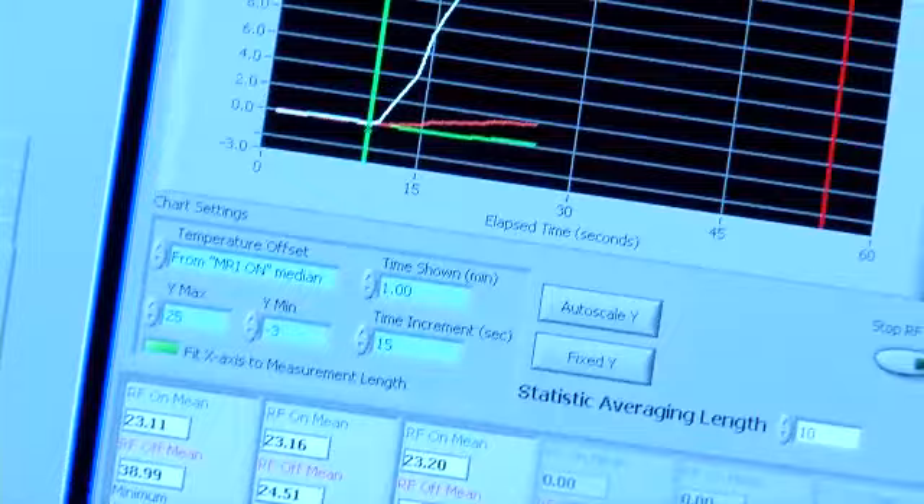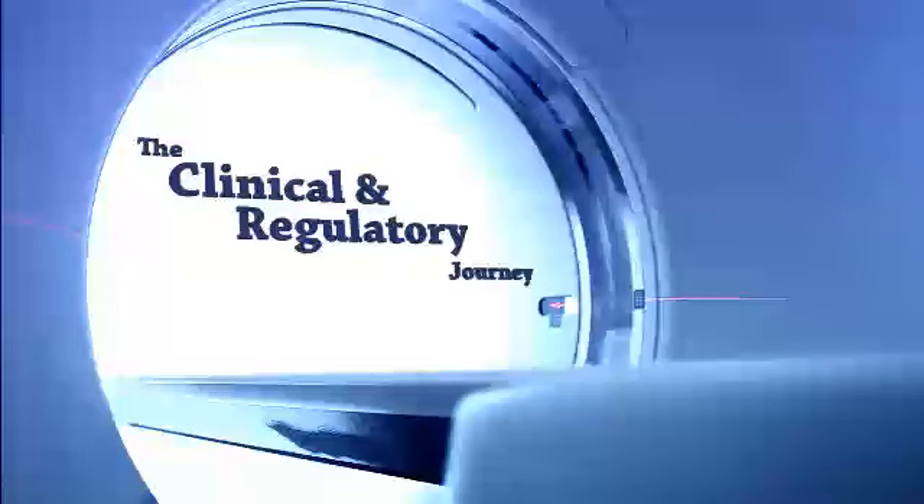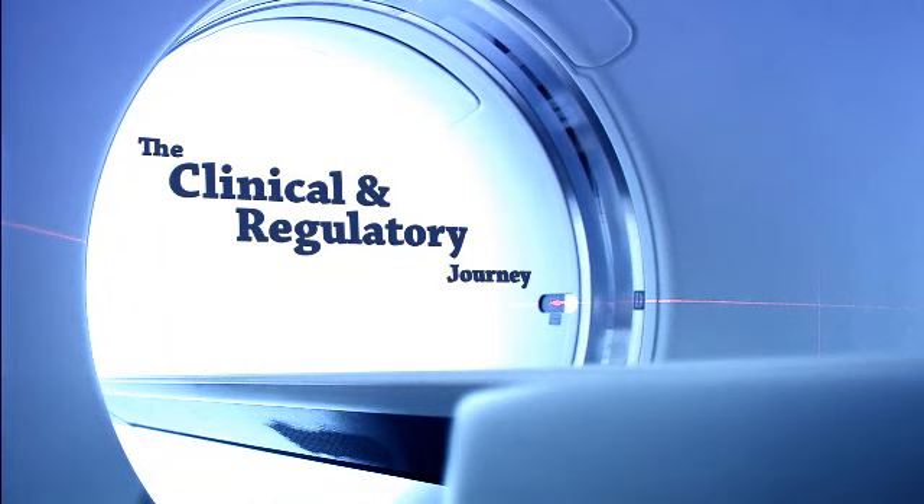We conducted over 1,500 measurements and compared each measurement to the simulated case. We saw very good agreement between our measured and simulated cases. We tested beyond physiologic limits — regardless of whether the MR scanner is capable of reaching physiologic limits or not, our device will be safe. This gave us confidence going into the relatively small human clinical trial. We had enough design margin and confidence that our solution was robust, with high confidence there would not be any complications.